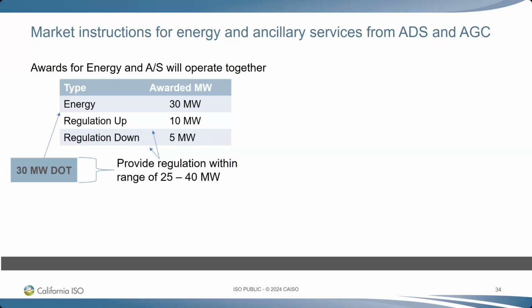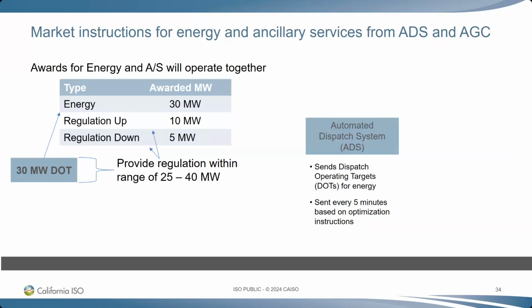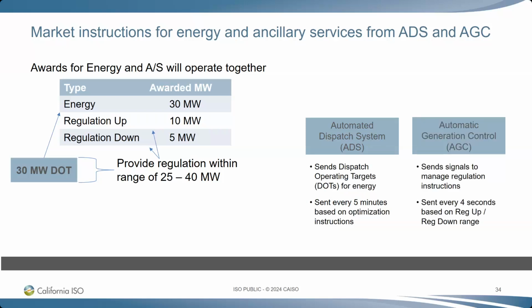The regulation provided will be within a range of 25 to 40, since regulation goes up and down. Based on those numbers, that gives you the range where it needs to go up an extra 10 megawatts and down to accommodate both. ADS provides the dispatch operating targets for the energy received every 5 minutes, and AGC sends signals to manage regulation instructions every 4 seconds.